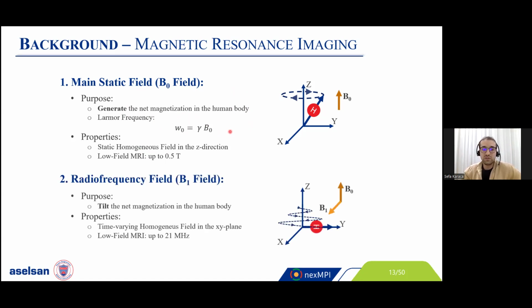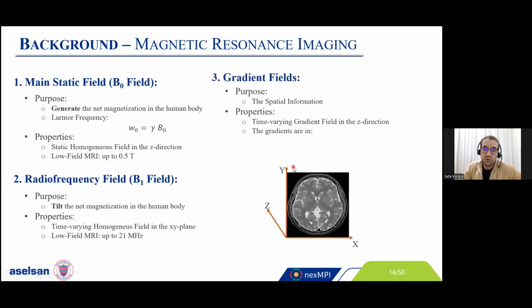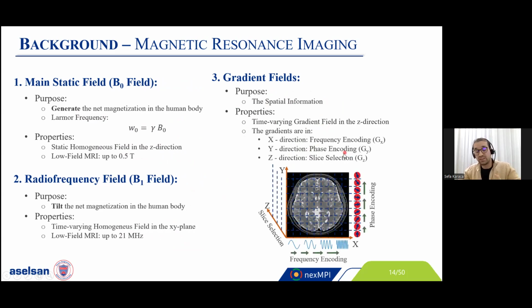The second field we need to generate is the radio frequency field, called the B1 field. The purpose of this field is to tilt the net magnetization in the human body. It's a time-varying homogeneous field in the XY plane, and the frequency of this field should match the Larmor frequency. If you are in the low field regime, in other words, if your B0 field is up to 0.5 Tesla, your frequency is in the range of megahertz. We should also create gradient fields in order to have the spatial information. These gradient fields should be in the X, Y, and Z directions, three directions, and they are called frequency encoding, phase encoding, and slice selection gradients. So in order to perform MRI, we need to generate these three fields.